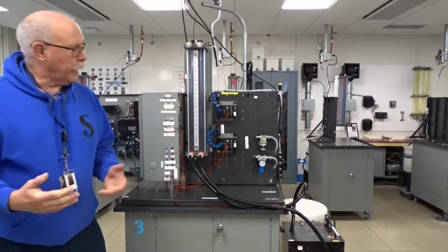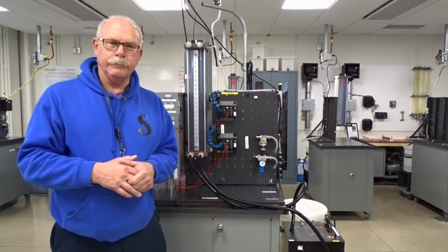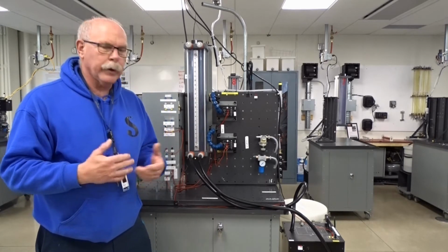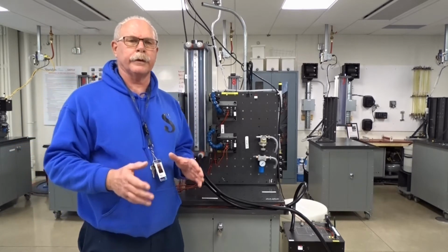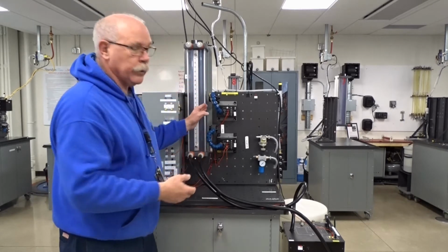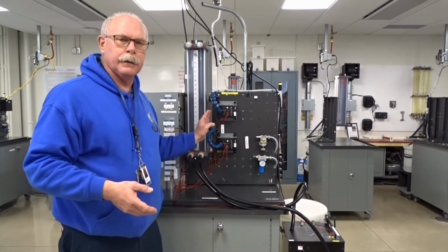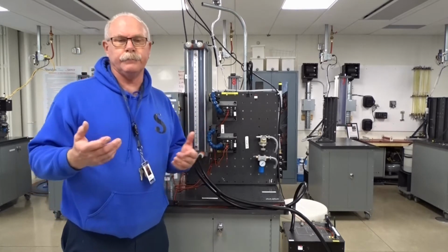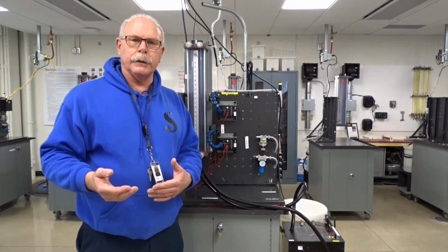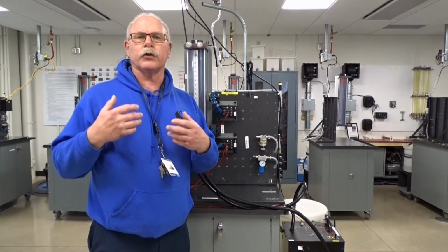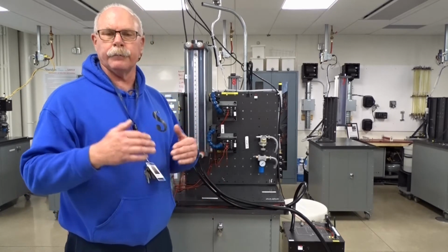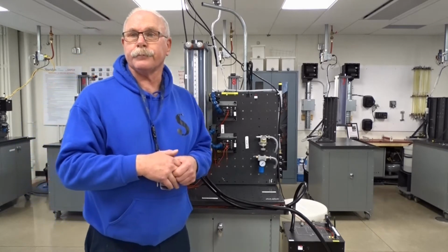Okay, so what we have here, lab 1, point level measurement. It's an on-off control. Point level because we're really only concerned with the level at any particular point. And in fact, in these 2 points, we have set up capacitance proximity detection switches. It's an on-off control because the corrective action is either there or not there. The pump is being turned on, and then it shuts off once it gets up to the upper range value. There are no in-between states.